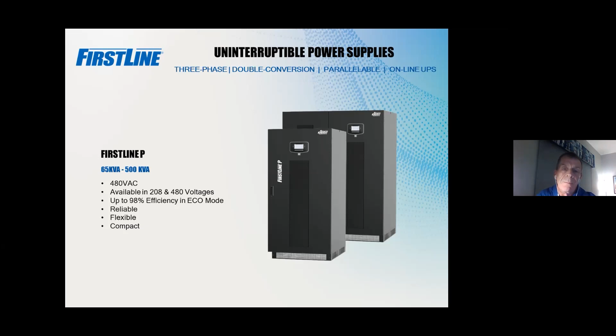We also have emergency lighting. One of the requirements we're seeing now, especially for new construction, and really for any type of refurb construction, is the need for emergency lighting to keep lights on for 90 minutes. This standard, the UL 924 product standard, requires that UPSs be sized to keep the lights on for 90 minutes in a facility.